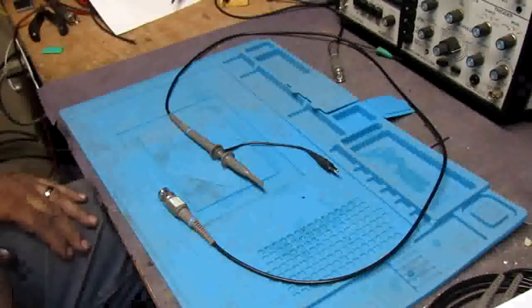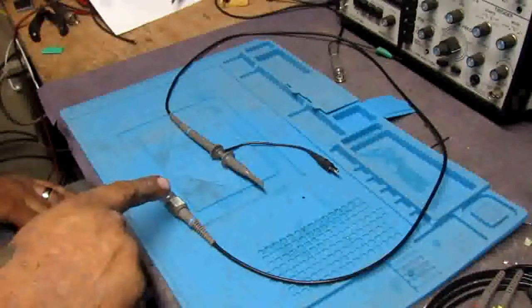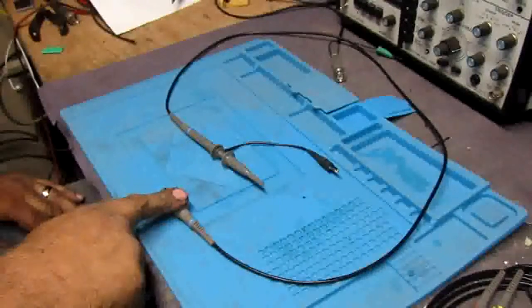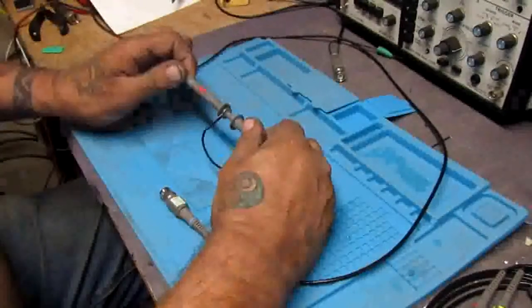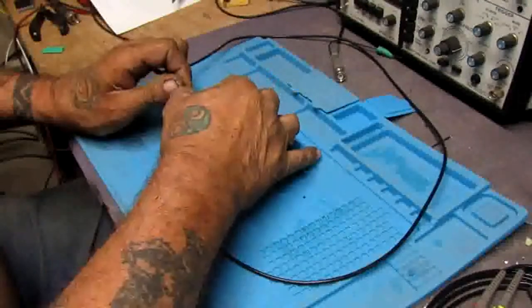Okay, so this is the P6100 probe. You have the BNC end and the probe end. The probe end has the 9 megohm resistor with the 1 and times 10 switch in it.